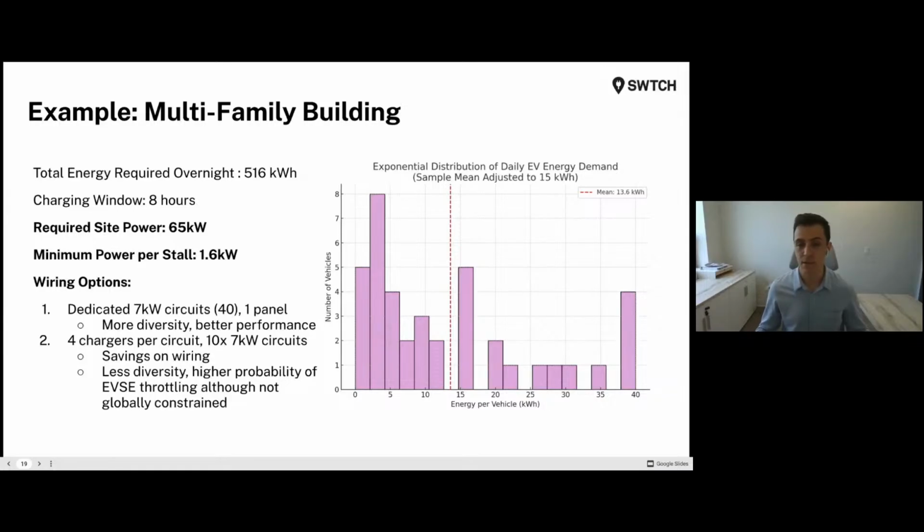Most of the time, probably 29 to 30 days per month, you're going to have the charger operating close to 7 kilowatts because some people get home early, some people get home late. There's plenty of time in the day to account for filling those vehicles. But in our design criteria, we're assuming a worst case scenario of I have to do it within 8 hours.